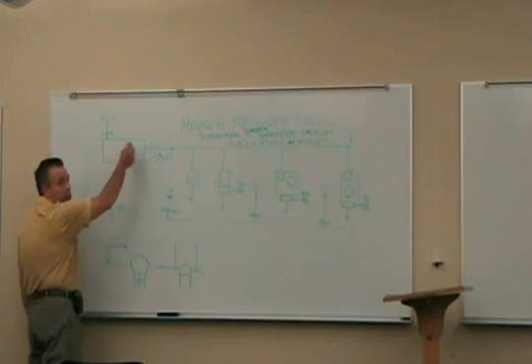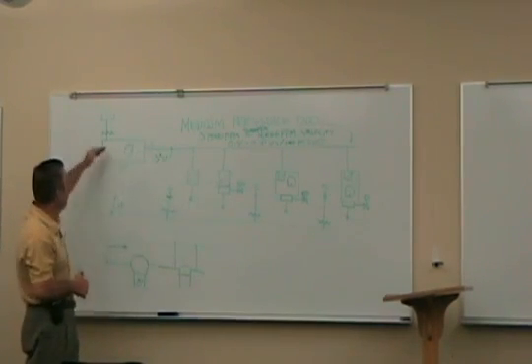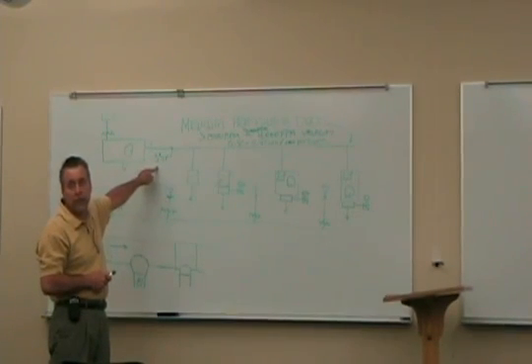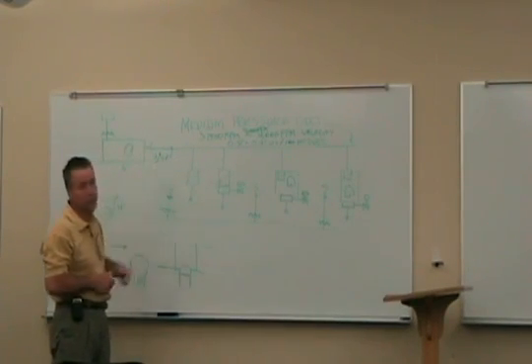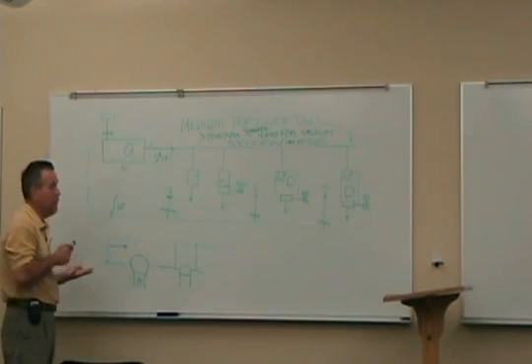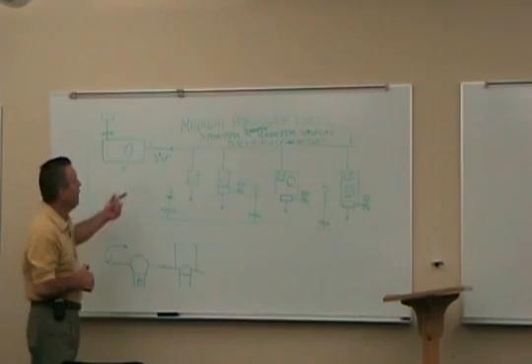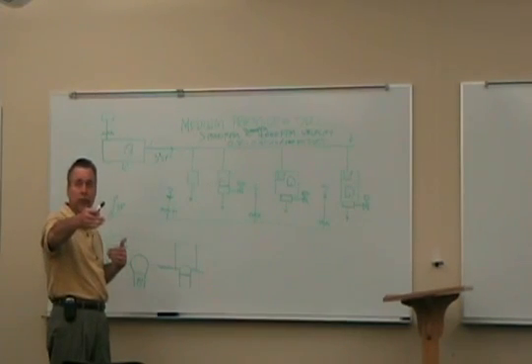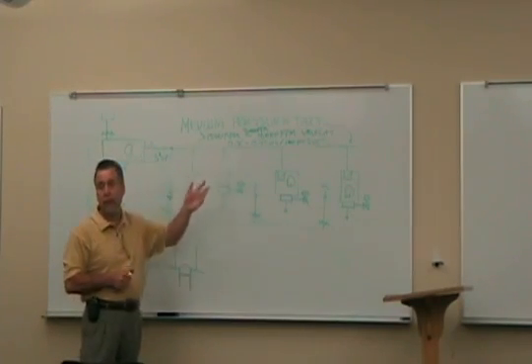But remember, we've got coils and filters, things in here, and we talked about the difference between the positive pressure and the negative pressure. So this should be listed in the specifications, may or may not be, but a sheet metal man would go to his SMACNA book and say, I want to build this duct for 3 inches of pressure. And he'll have options of different gauges, 20 gauge, 18 gauge, 16 gauge, more like probably 20 gauge. And SMACNA will tell him how to build it, what kind of seams to make in it, and how far to specify his reinforcement. Reinforcement might be 4 feet on centers, it might be 8 foot on centers.